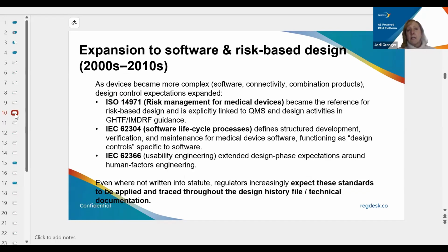From there, we've also seen additional expansion to other requirements. Software is a key area, and also risk-based design. So additional standards have come into play. ISO 14971 is for risk management of medical devices. The IEC 62304 talks about the software lifecycle processes, and then usability engineering as well. So making sure that manufacturers are looking at exactly how users will utilize their products in the clinical setting, and ensure that they're addressing those usability requirements as well.